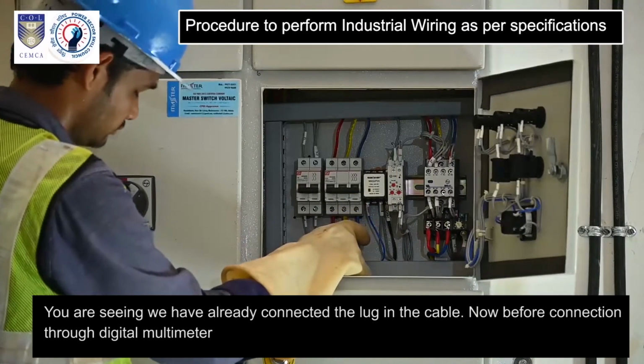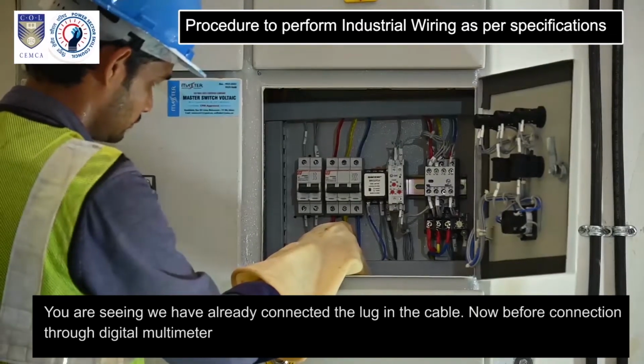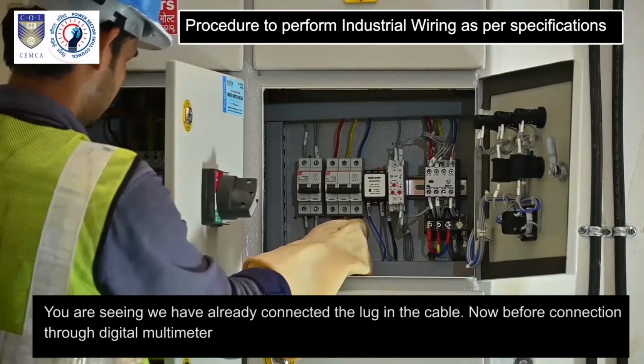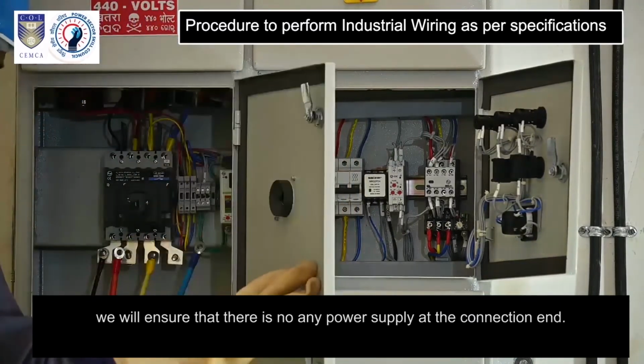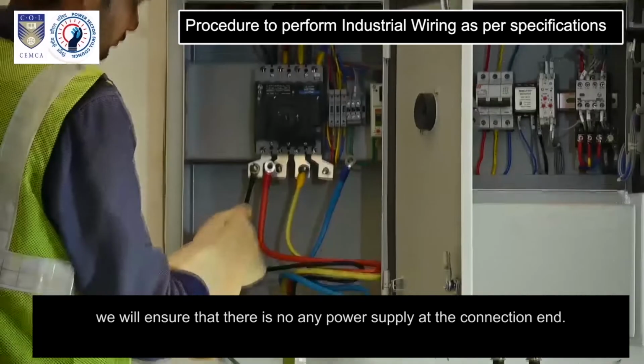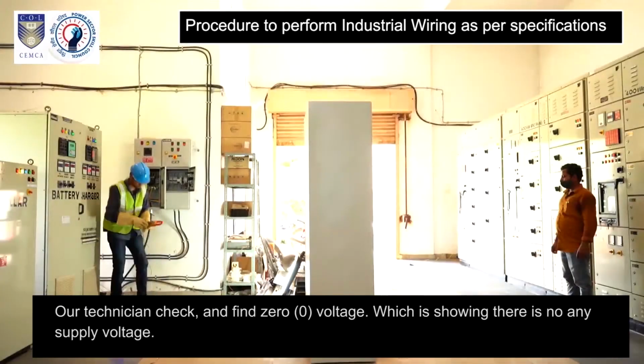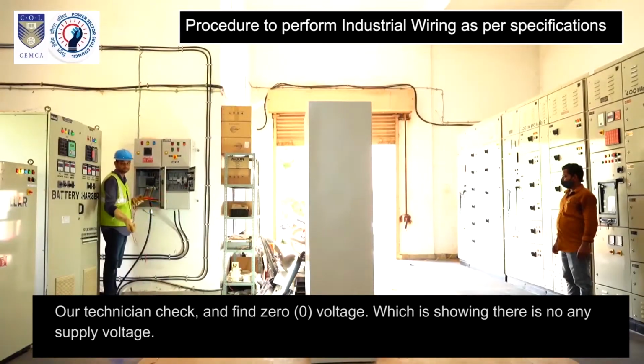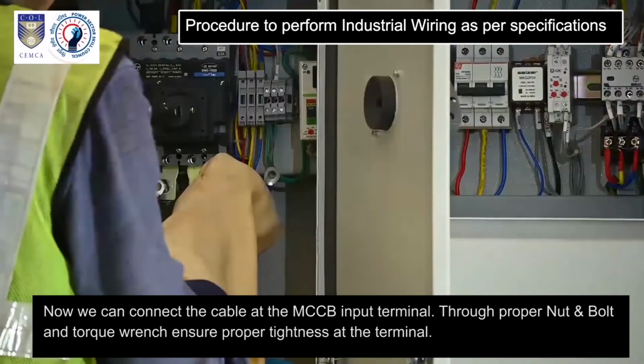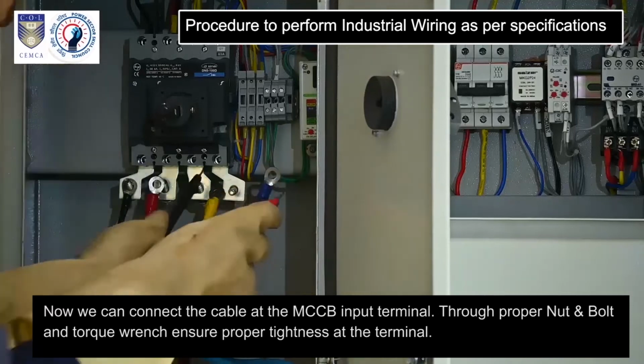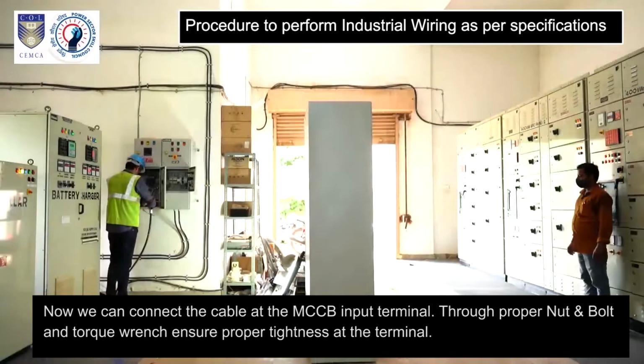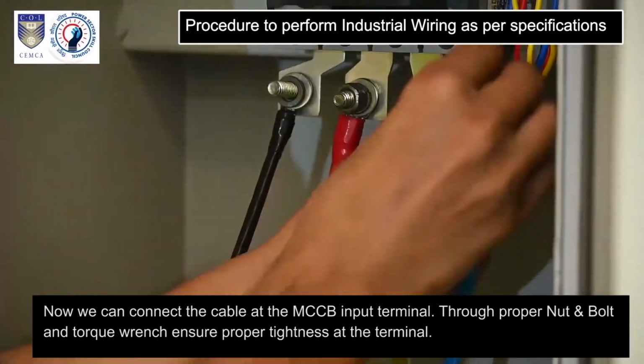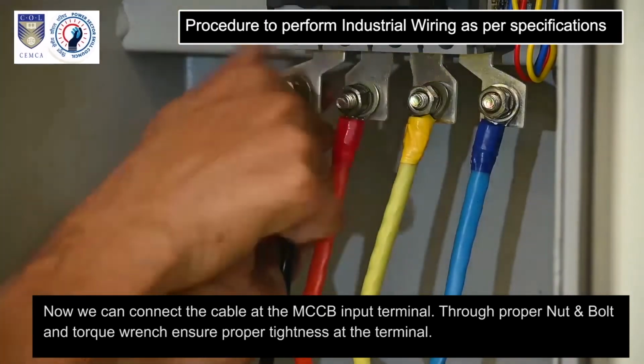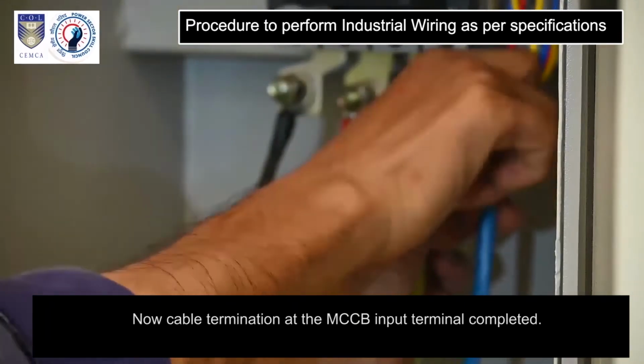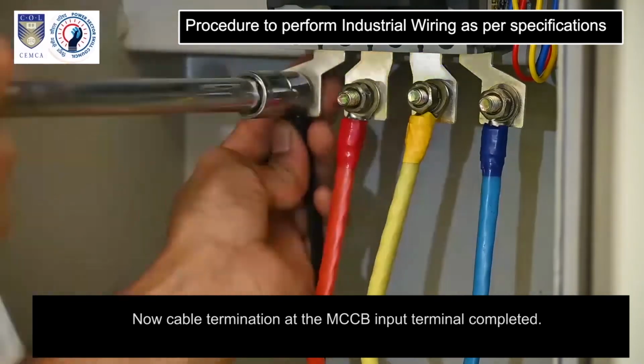You are seeing we have already connected the lug in the cable. Now before connection, through digital multimeter, we will ensure that there is no power supply at the connection end. Our technician checks and finds 0 voltage, which shows there is no supply voltage. Now we can connect the cable at the MCCB input terminal through proper nut and bolt, and a torque wrench ensures proper tightness at the terminal. Now cable termination at the MCCB input terminal is completed.